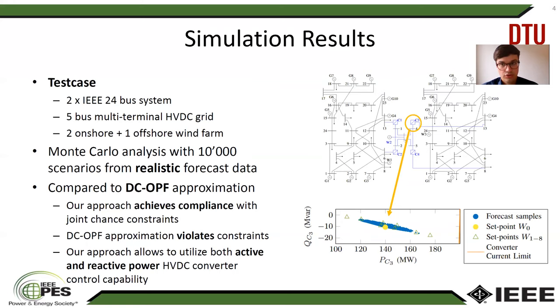We compare our approach to an existing approach using the DC-OPF approximation, and find that our approach achieves compliance with the joint chance constraints whereas the DC-OPF approximation violates the constraints — that is, the empirically observed violation probability is higher than the specified maximum allowable. More importantly, our approach allows utilization of both active and reactive power HVDC converter control capabilities. On the right, for converter C3, we can see that for different realizations of wind farm forecast errors, both active and reactive power are adjusted to maintain security.